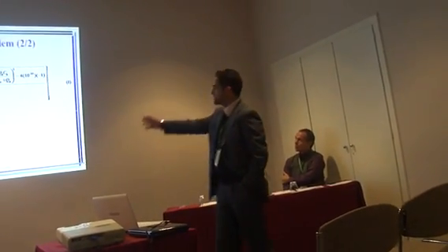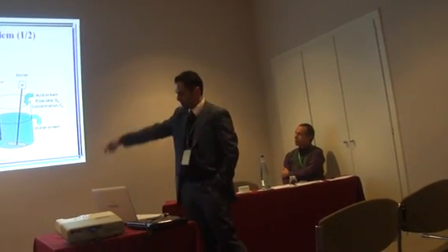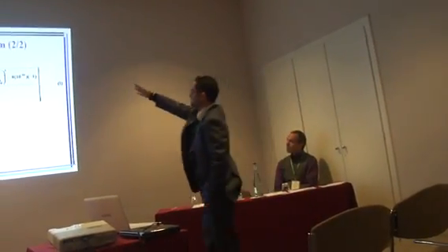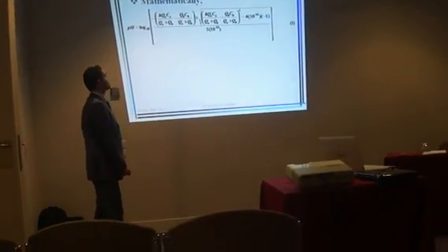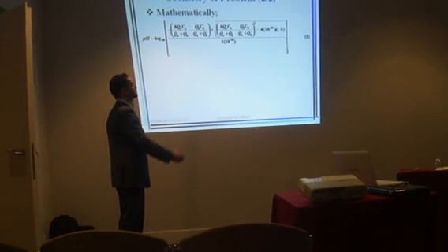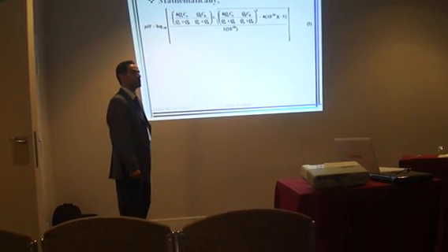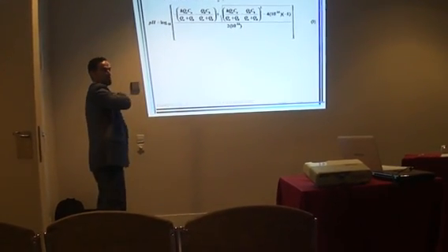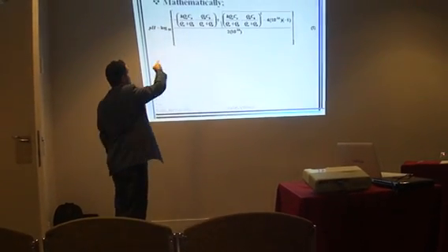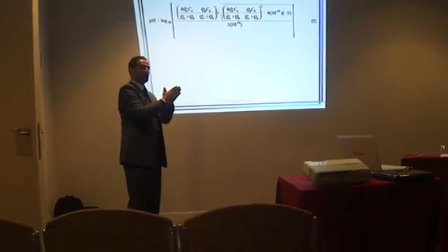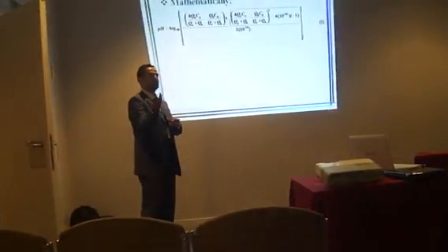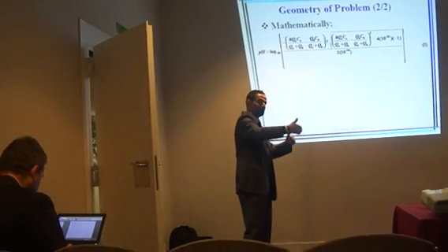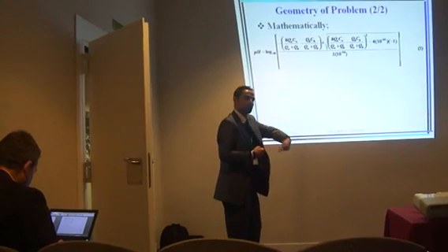The second, as you see, after derivation and reformulation of the three equations, we can get, and this is not an equation you can find in the literature, the relation between pH and acid flow rate, acid concentration, QA, CA, base flow rate, base concentration, QB, CB. I'm concerned with the acid flow rate, QA. So this relation gives a direct nonlinear relation between pH, my process variable, and the manipulated variable to be measured, which is QA. Now I would measure the flow with flow sensors, which are much cheaper than pH meters, and then in the second stage I could estimate the pH value. So finally I have an estimated pH value to be fed back to the controller.